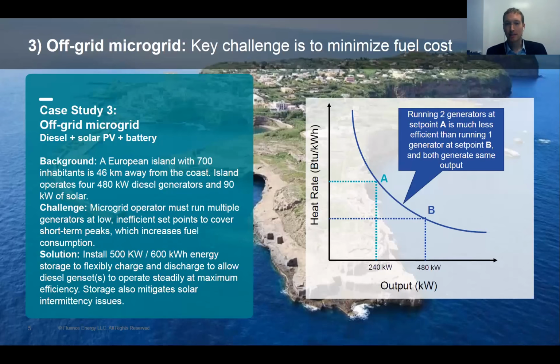And they have four diesel generators on the island. In order to meet short-term peaks in demand, they were forced to run one or two of the generators at a minimum load, so they could ramp up quickly if there's an unexpected jump in demand. As I show on the graph on the right for the more technical folks out there, you don't really want to run your generators at min load because from a fuel efficiency perspective, it's not very good.